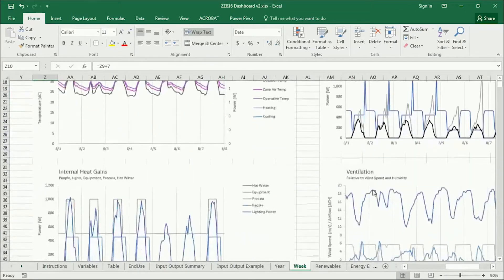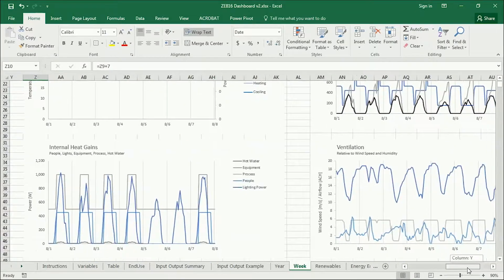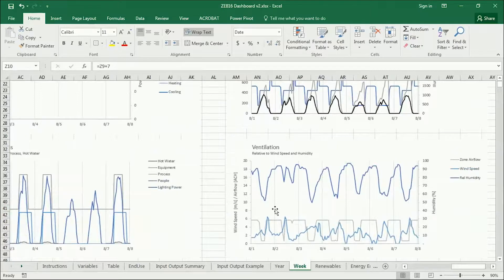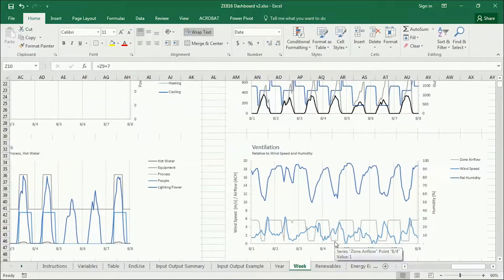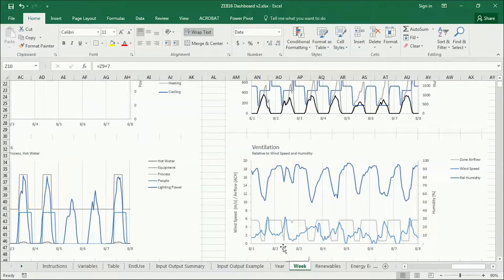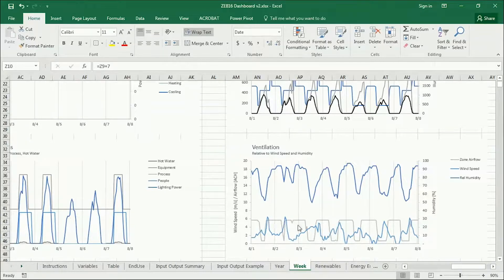We can check this over here on the right. You can see a diagram of ventilation against wind speed and humidity. This gray line is the ventilation, and you can see that ventilation is by and large coming on at night and then dipping way down during the day. In the midday period you can see that ventilation is turning off. Here on August 2nd, it looks like the ventilation just turns off for one hour, and the rest of the time it looks like it's on.